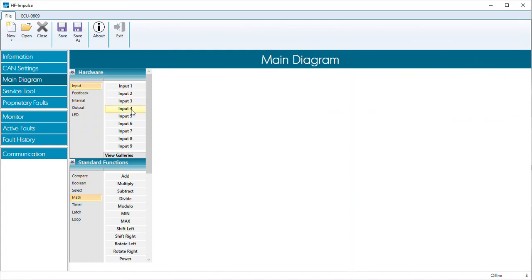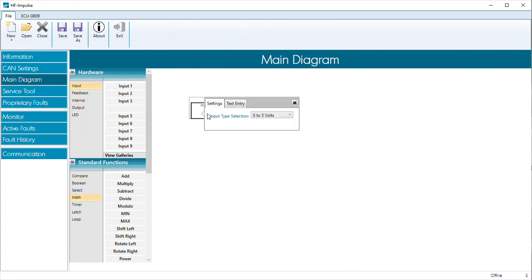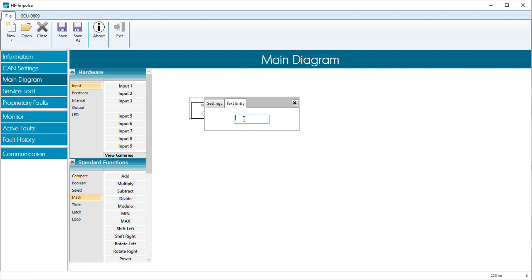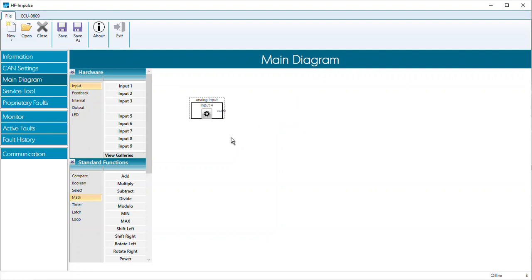So if we bring in input four and touch the little gear, we see that I can configure it for zero to five volts, zero to 20 milliamps, or a digital input. I'm going to go ahead and give it a value — I'll set it to analog input. Then X out to give me back to my programming space.